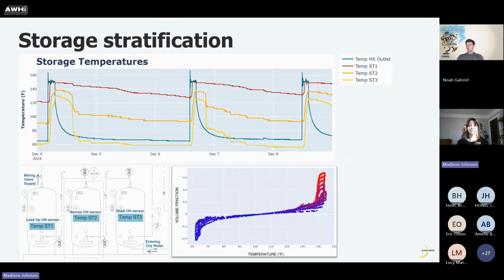We can see this in some field data from that first QAHV site in Portland. In the top plot, the teal line is our heat exchanger outlet temperature. When our system is on, it's producing 150-degree water. Our warmest storage tank is at 150 degrees, but our middle tank and our lower tank we see about 140 and 130 degrees. So this is going to drive a different stored energy than if the entire portion of the tanks were 150 degrees. To account for this, the next improvement Ecotope would like to make to Ecosizer is to introduce a stratification factor, which would help bring Ecosizer's estimates closer to what we see in the single draw tests.